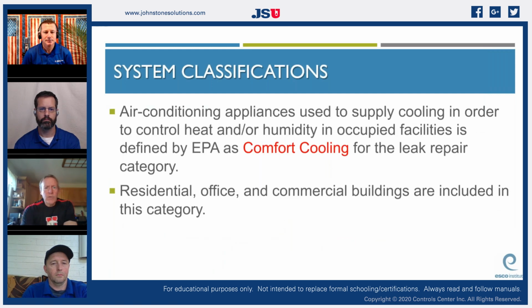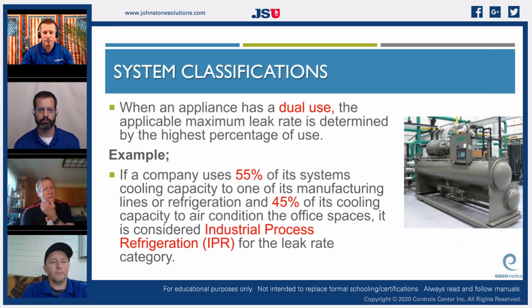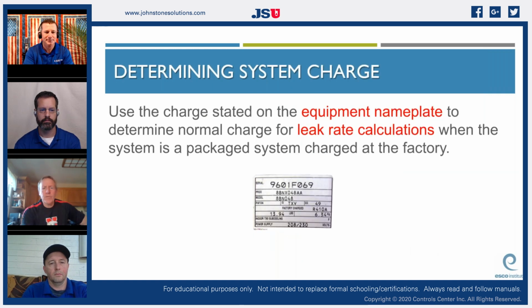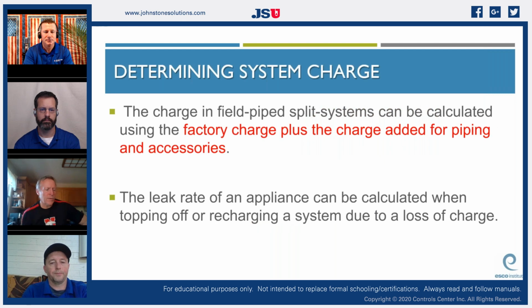So the lowest is comfort cooling, air conditioning. It's at 10%. This is systems holding over 50 pounds of refrigerant, by the way. Commercial refrigeration is 20%. IPR is 30%. But the best place to find the type of refrigerant in it and the amount of refrigerant is the equipment nameplate. And you'll need that for leak rate calculations. But remember this, back to the residential side. We have a nameplate that tells us what the factory charge is, but that's only good for 15 feet of line set and the smallest matching evaporator, by the way, something they don't actually usually tell you. But if you had a system that had 5 pounds charge in it and a 30-foot line set, then the total charge for leak rate calculation would be 5 pounds 9 ounces.